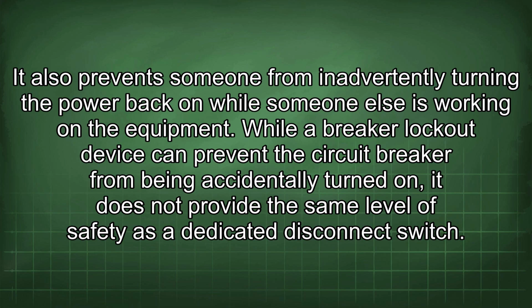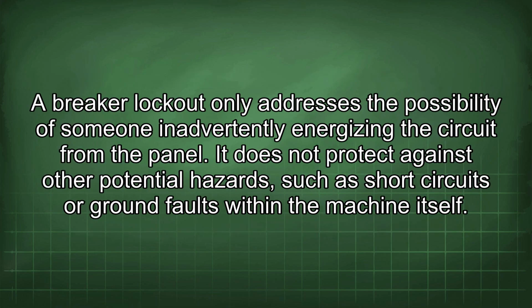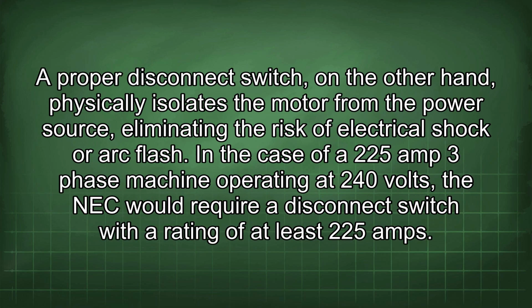While a breaker lockout device can prevent the circuit breaker from being accidentally turned on, it does not provide the same level of safety as a dedicated disconnect switch. A breaker lockout only addresses the possibility of someone inadvertently energizing the circuit from the panel. It does not protect against other potential hazards, such as short circuits or ground faults within the machine itself. A proper disconnect switch, on the other hand, physically isolates the motor from the power source, eliminating the risk of electrical shock or arc flash.